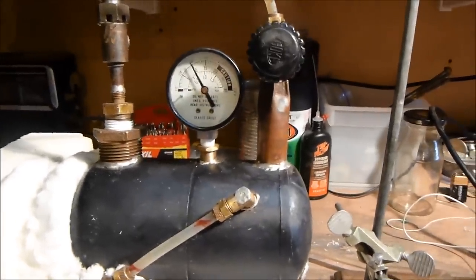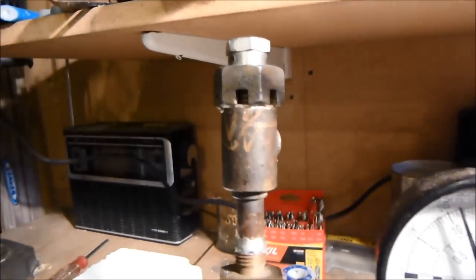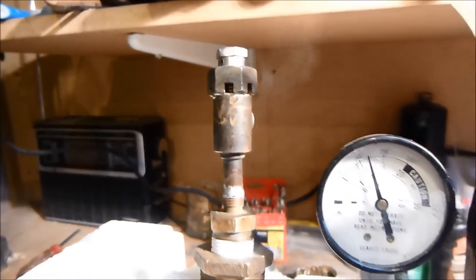About seven minutes, seven minutes 30 seconds it takes for it to get up to temperature where the pressure is really starting to build. So it's 15 psi already and as you can see the pressure relief valve's leaking a little bit. It always does.